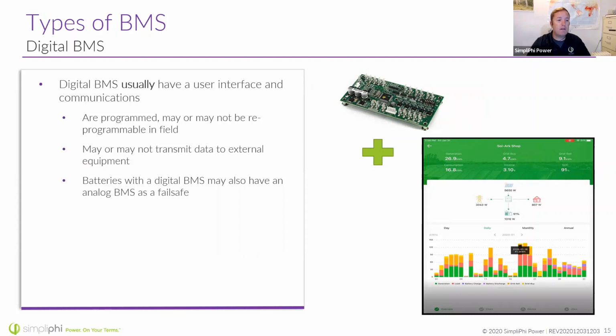If we can measure amps in and amps out through a shunt and transmit that data to the equipment, we get a much more accurate reading. Also, we can read the voltage at the battery cell level and transmit that data, giving us a higher level reading.